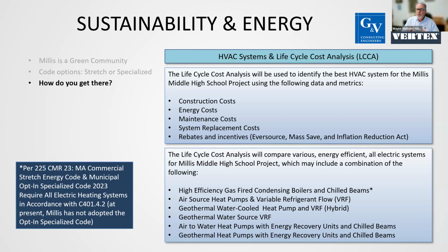When we do these life cycle costs, besides the costs that go into it, we also evaluate six generally accepted good HVAC systems. High efficiency gas-fired condensing boilers coupled with either chilled beams or displacement ventilation -- this is a more conventional system, but still very efficient, with boilers running at 96 to 98% efficiency. The HVAC systems are modern, and everything has variable frequency driven fans and pumps, so the speed of equipment is based on the load of the building and the CO2 within the building.